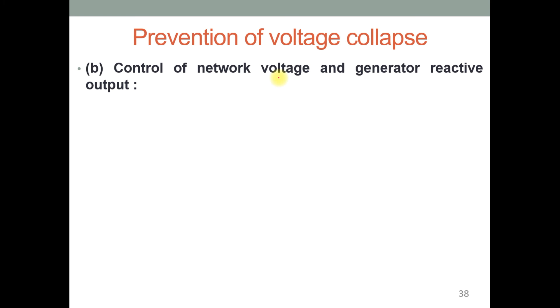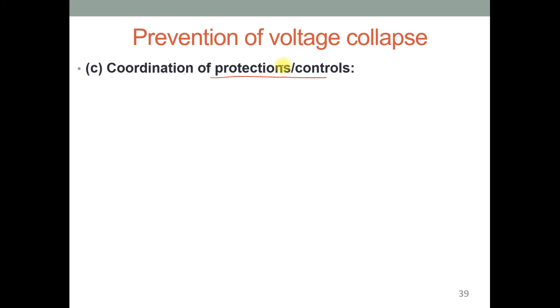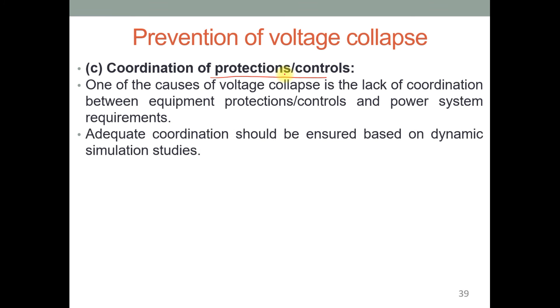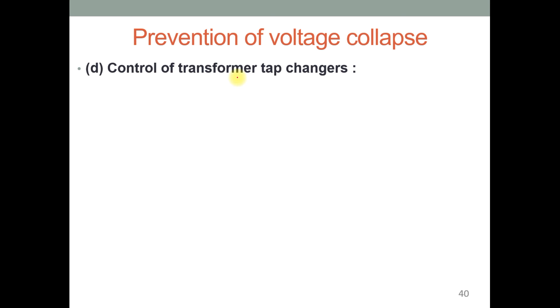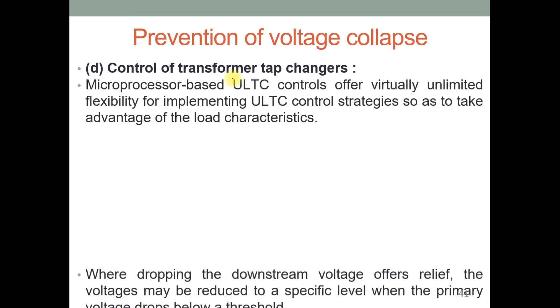Then control of network voltage and generator reactive power output using OLTC and AVR. Then coordination of protection and controls when a contingency takes place. This is the important thing. Clear? So coordination between your protection schemes. Then the control of transformer tap changers, and under voltage load shedding.